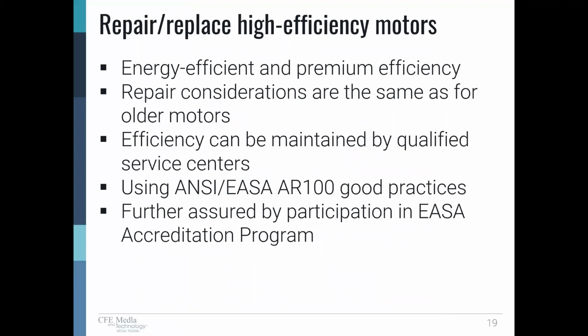So, energy efficient and premium efficiency motors. What we mean by energy efficient is a term from the U.S. Department of Energy's regulations that goes back to the Energy Policy Act of 1992. They were also called EPACT, E-P-A-C-T motors. That's our energy efficient motors. In the global, metric world, the International Electrotechnical Commission, IEC, designation for those motors is IE2. Then we have premium efficiency. Before there was federal legislation, the motor manufacturers, NEMA, came up with what they called NEMA Premium. These are now the premium efficiency motors, with the metric global equivalent being the IE3 motors.